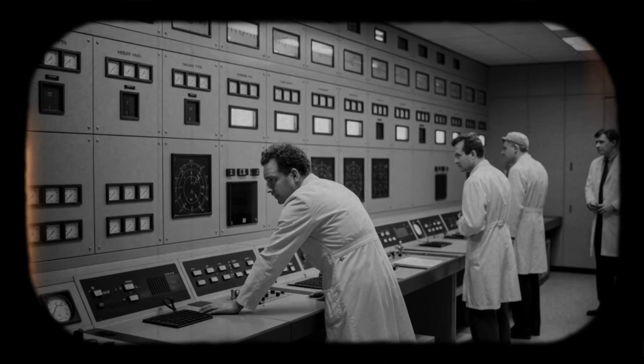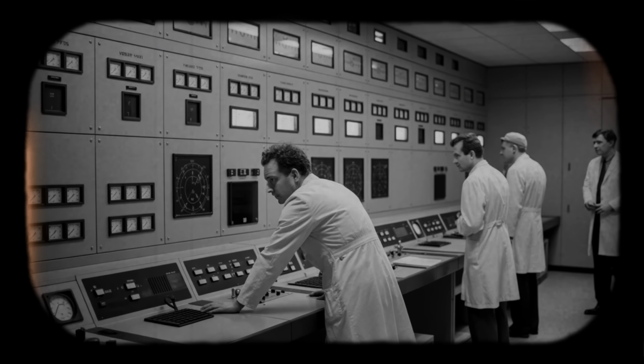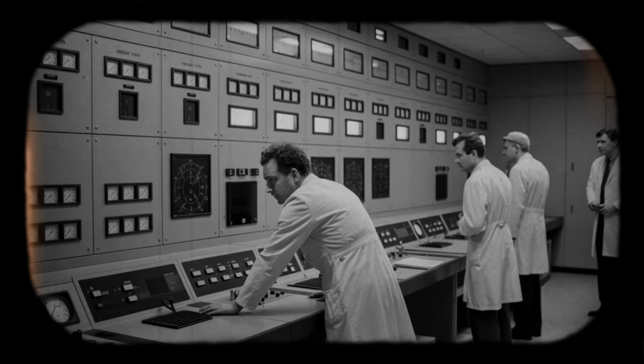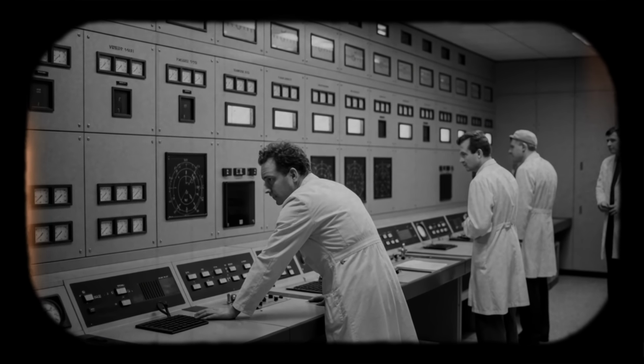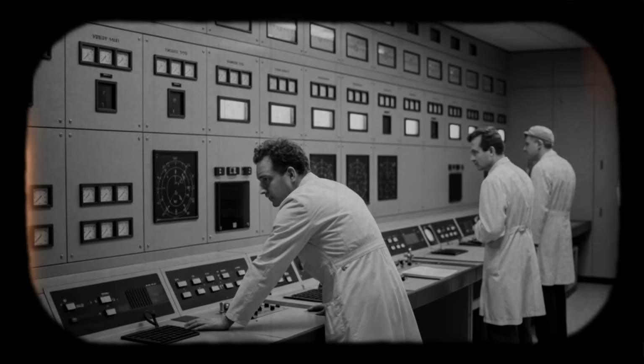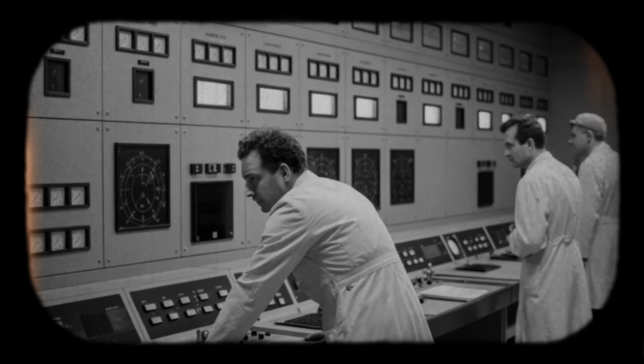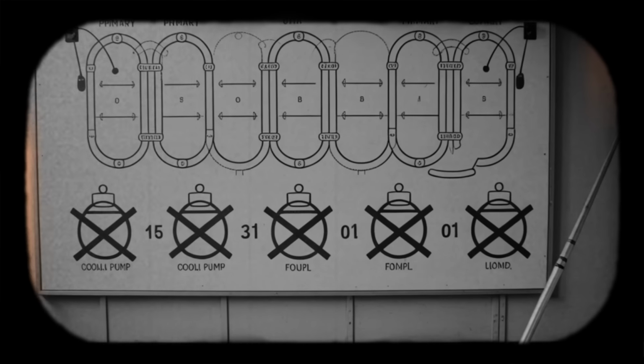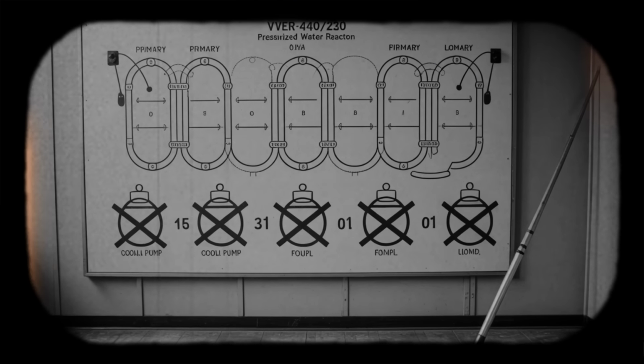Firewater systems required manual actuation. Segmentation of the turbine hall and cable tunnels was limited. Robust fire barriers between some compartments were absent or inadequate. The design had not anticipated this scenario, a self-sustaining fire in cable insulation propagating along trays with manual firefighters as the only barrier.